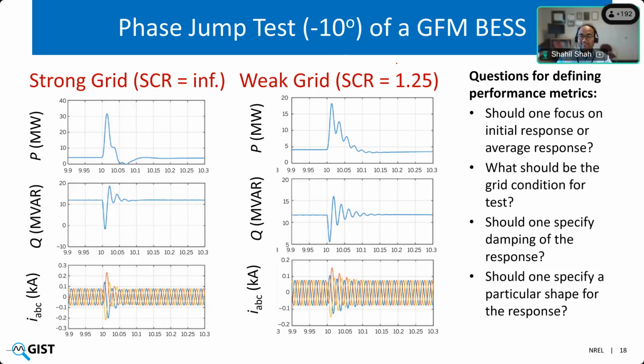Here is the response of a grid forming BESS to a -10° phase jump. This test is performed using a vendor supplied EMT model, the black box model. We see the active power response, reactive power response, and the response in the output currents. The active power jumps during this negative phase jump. It increases by around 25 megawatts from the pre-disturbance level, and after around 50 milliseconds or so, it comes back to the pre-disturbance level.